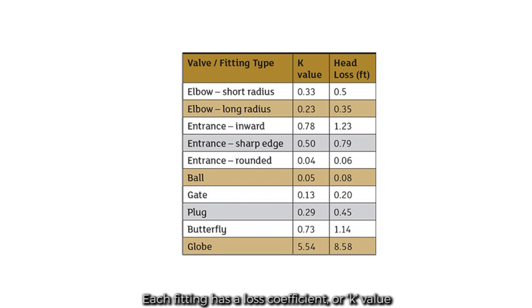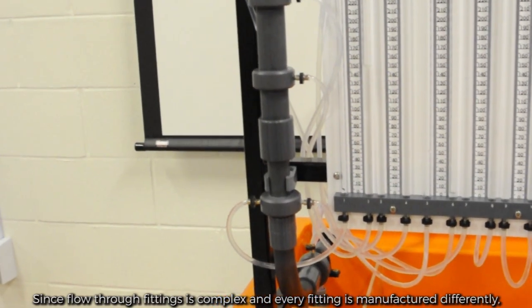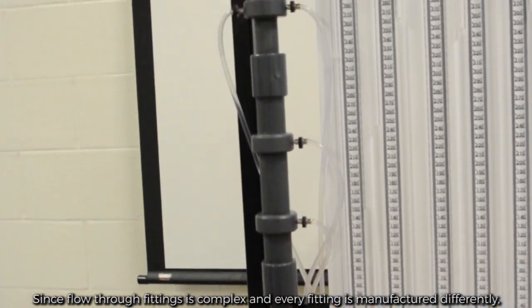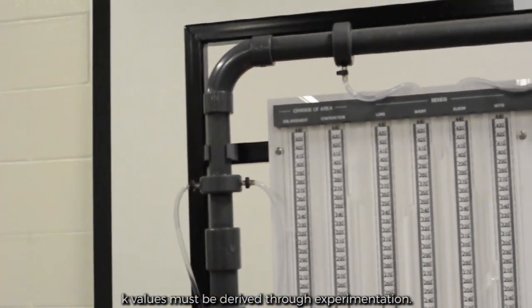Each fitting has a loss coefficient, or k-value, that can be used to calculate the head loss that it caused in the system. Since flow through fittings is complex and every fitting is manufactured differently, k-values must be derived through experimentation.